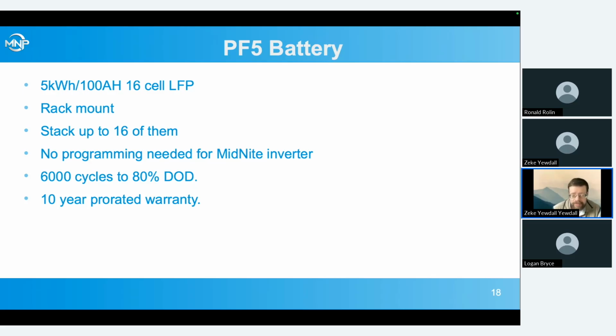Similar, other than that, we can stack 16 of them, no programming needed, and these have a 10-year warranty and 6,000 cycles. These rack mount ones, we need at least 3 batteries per inverter. The wall mount ones, you can do 1 battery per inverter. Better is to have 2 of the wall mounts per inverter or 4 or 5 of the rack mounts per inverter to really get full, if you're really taxing that inverter at full surge capacity. But we do allow using 3 of the rack mounts and 1 of the wall mounts per inverter.